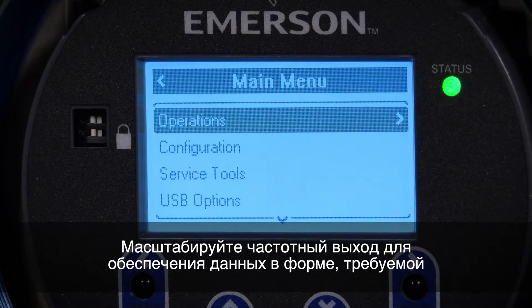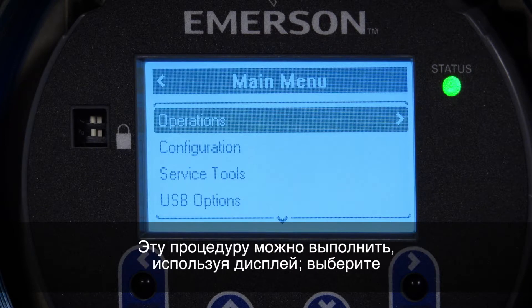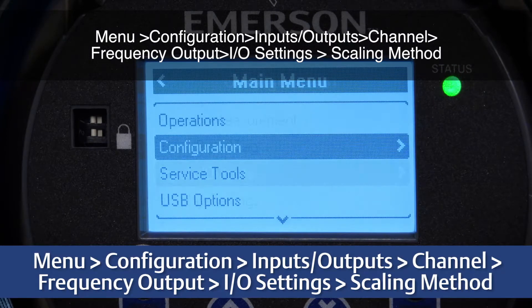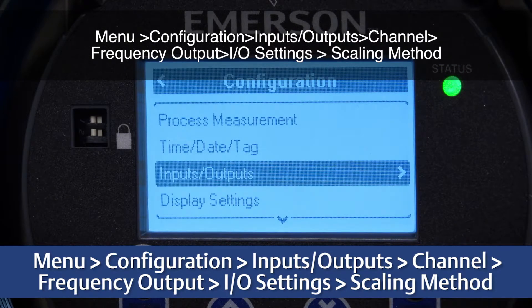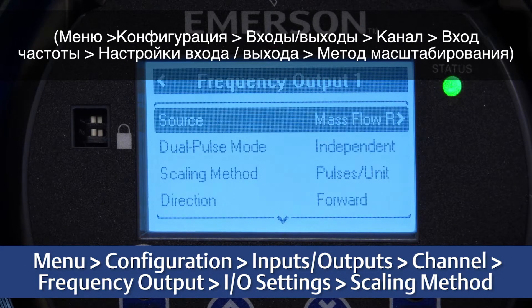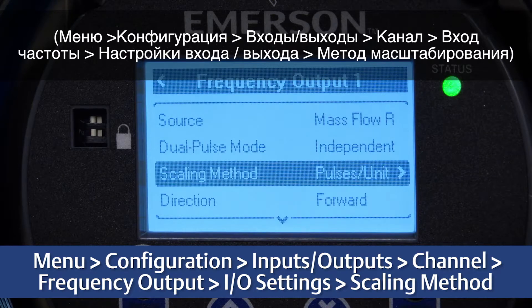Scale the frequency output to provide the data in the form required by the device receiving the transmitter frequency. This can be completed by using the display and selecting Menu, Configuration, Inputs, Outputs, Channel, Frequency Output, I.O. Settings, Scaling Method.